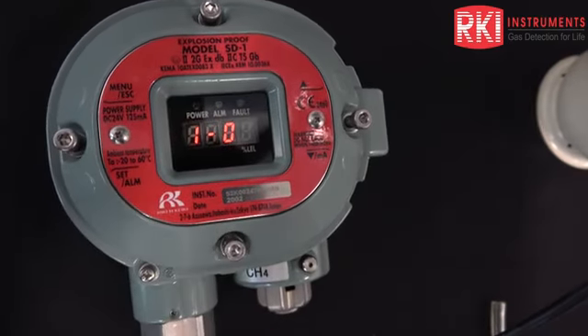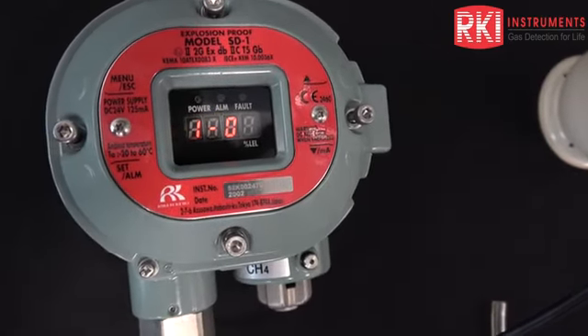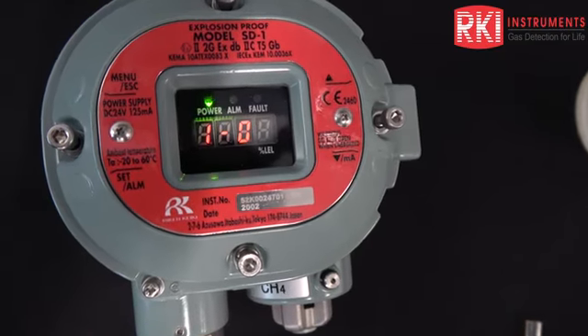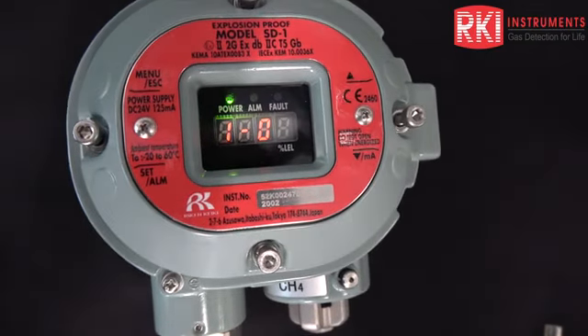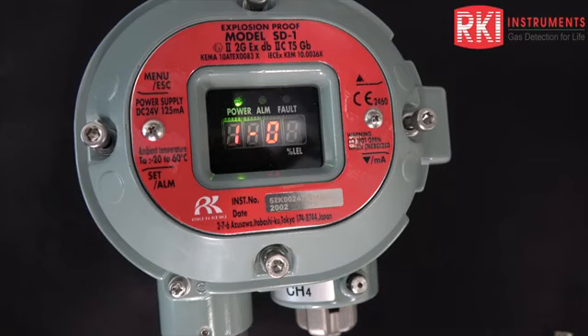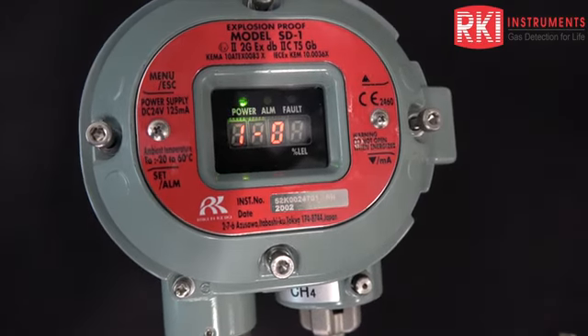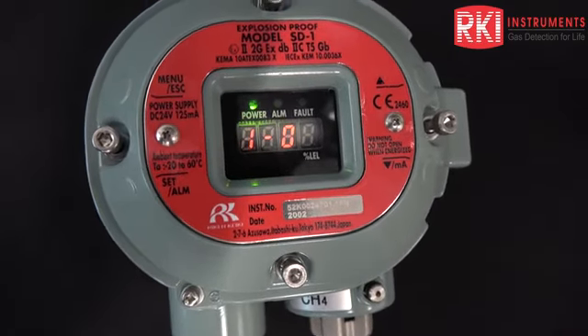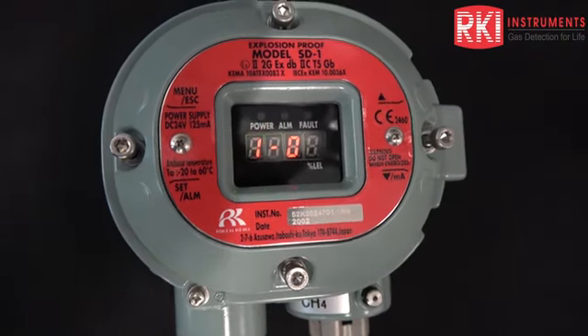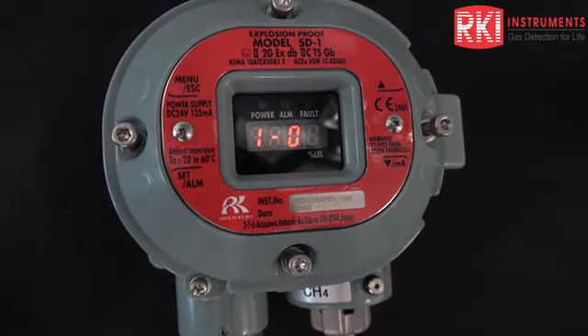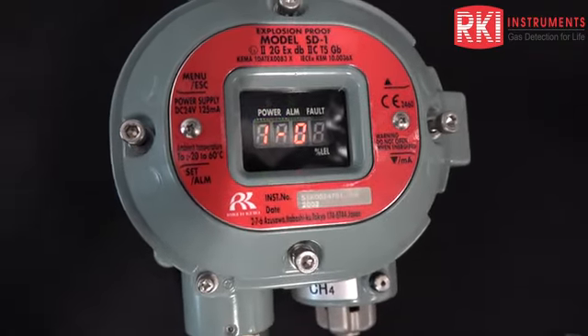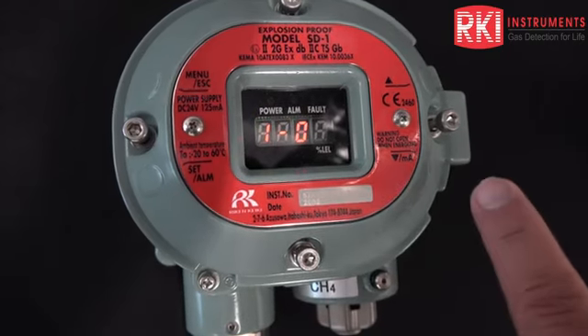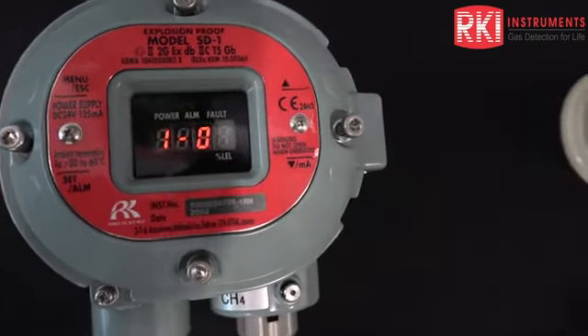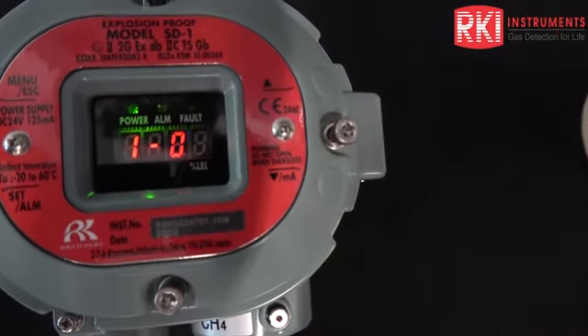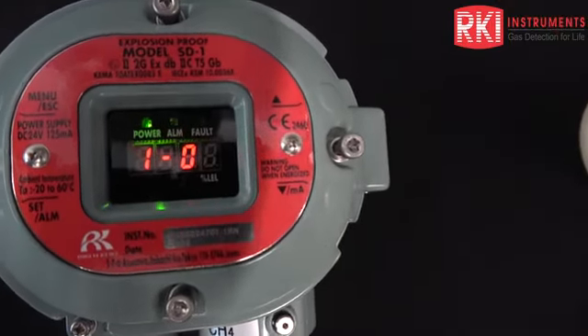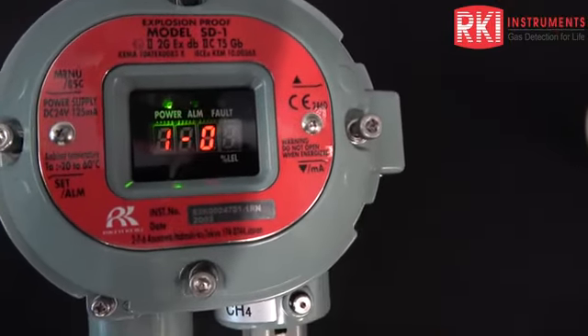Okay, and then that brings up a setup mode, so to speak, or a confirmation mode of 1-0. And then your pilot light is now blinking, so that shows you you're not in a gas detection mode any longer. So you're basically in a maintenance mode, so to speak. All right, so now I can use either of these other two pads on the other side. The top button would be to take values upward, and this bottom pad would be to take values downward.